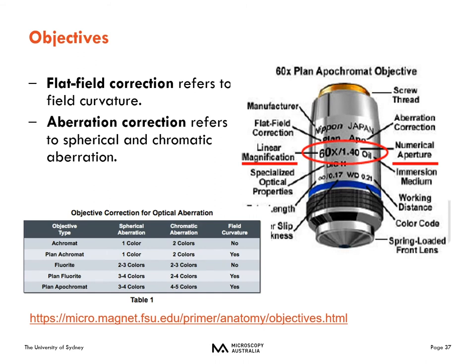The objective type listed on the barrel indicates corrections for optical aberrations — field flatness, spherical aberration, or chromatic aberration. 'Plan' means correction for field curvature. 'Achromat' has chromatic aberration correction but no spherical aberration correction. 'Fluorite' lenses have some chromatic and spherical aberration correction. 'Apochromat' has the most spherical and chromatic aberration correction.